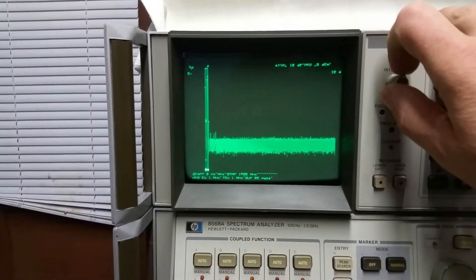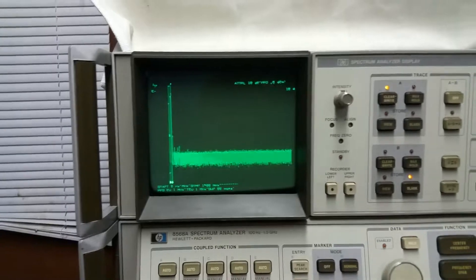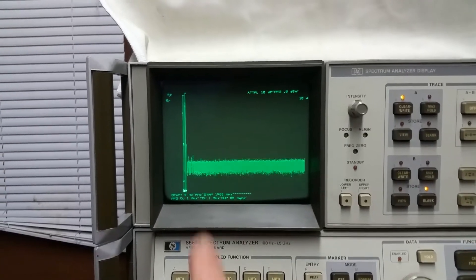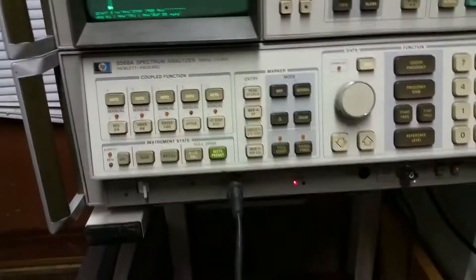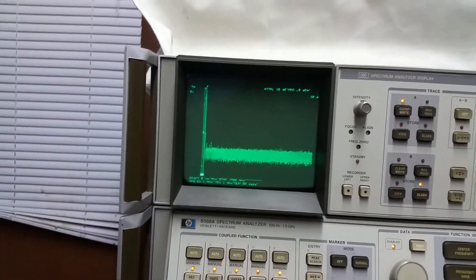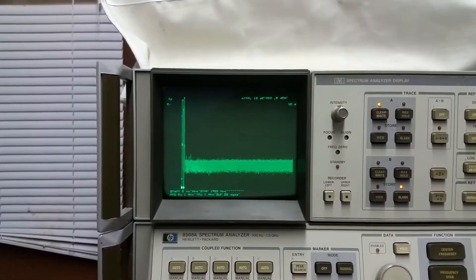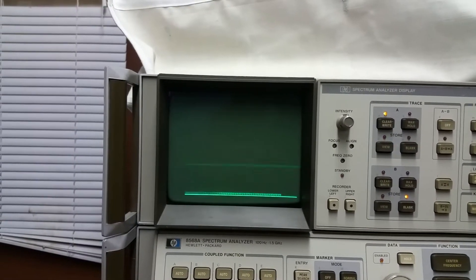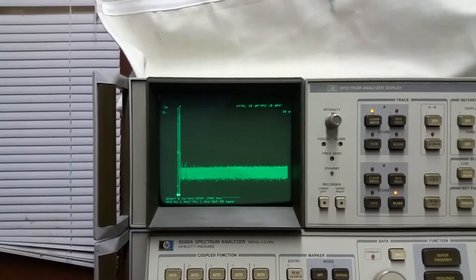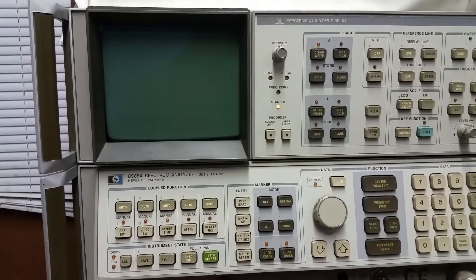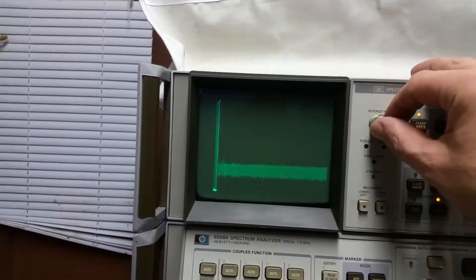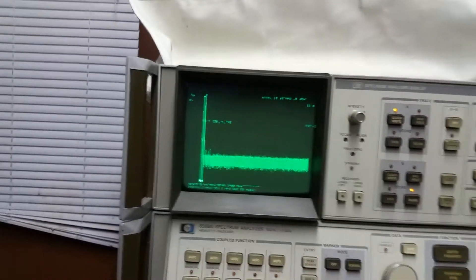It started off slightly differently this time, with the display flashing, but it's deteriorating. Now we've got this scrambled data on the screen, the instrument one failure. Resetting the system doesn't make any difference - it looks like it initially maybe clears, but you never get the graticule back. If you turn the power off and recycle that...